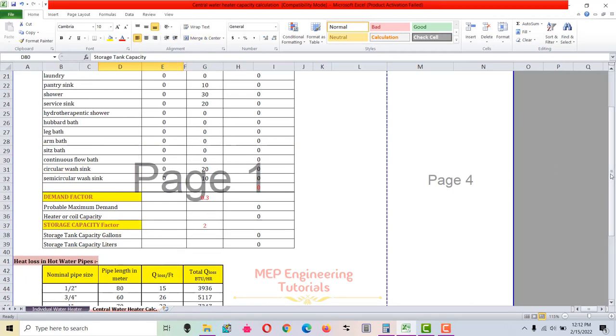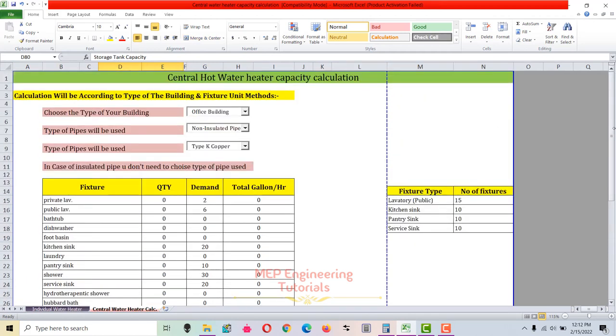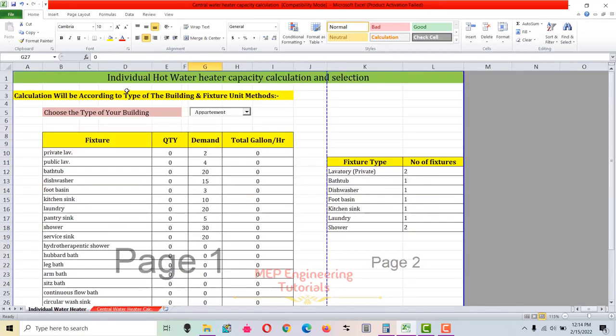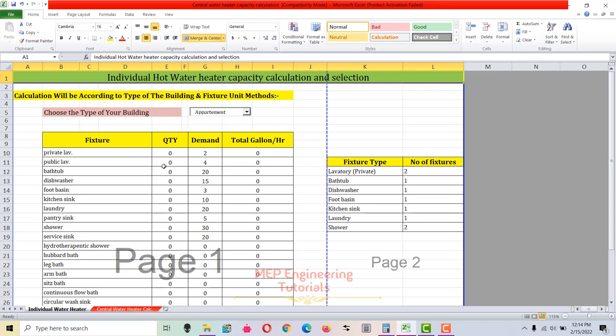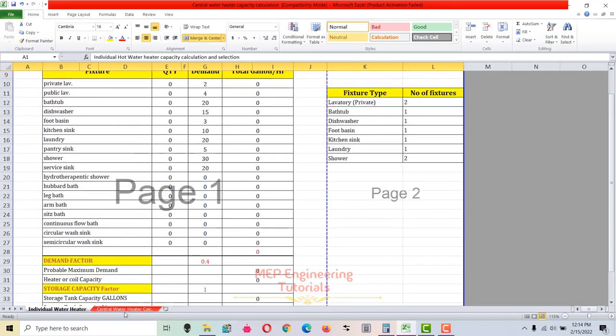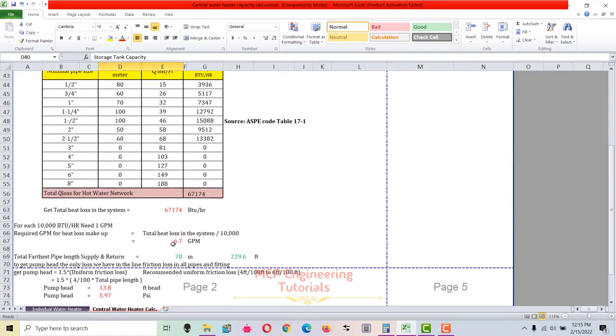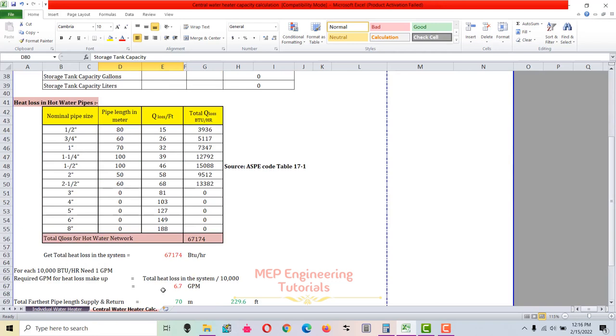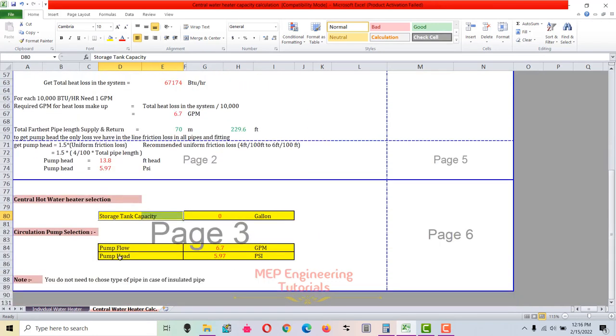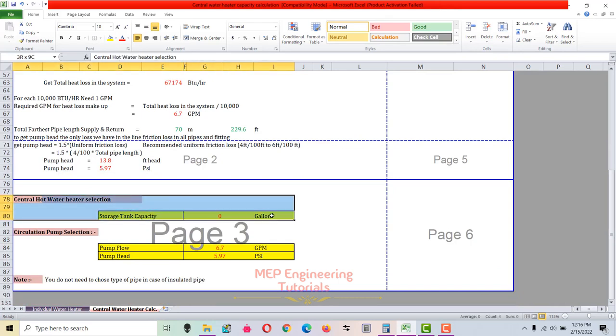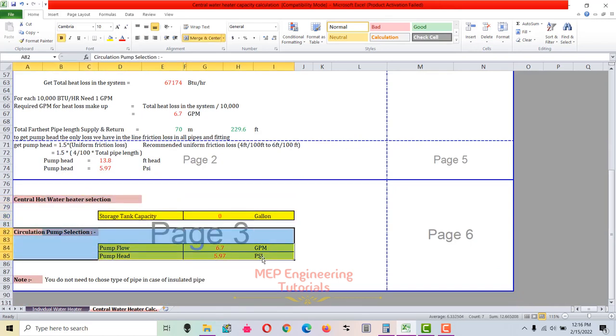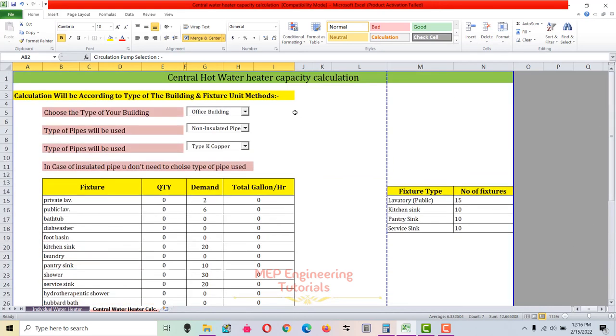The second spreadsheet is related to the central hot water heater capacity calculation and selection. An individual hot water heater supplies hot water to single or multiple spaces without any recirculation system. A central hot water heater supplies hot water to multiple spaces within the building, has large capacity, and includes a hot water recirculation system. For the central hot water heating system, we will calculate the central hot water heater capacity, storage tank capacity, as well as the circulation pump flow and head.